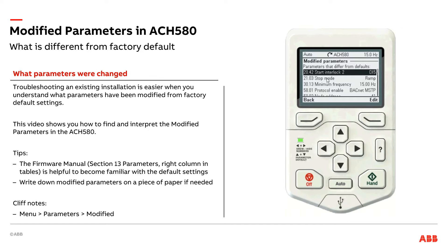I can see that I've got start interlock two, so I have a second safety wired and configured for digital input five. Normally, I just have start interlock one, the factory default, on digital input four. So maybe this is an air handler and I have not only a high static safety on DI four, but maybe I've got a freeze stat up here in Wisconsin on DI five.